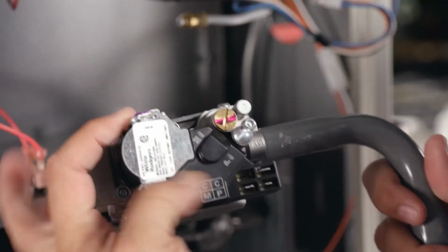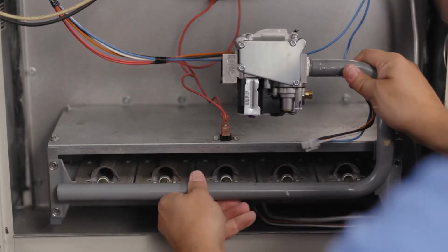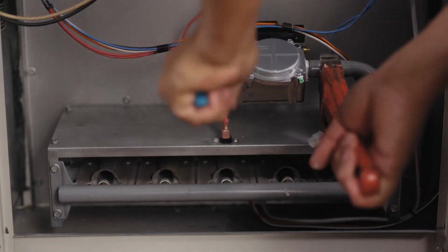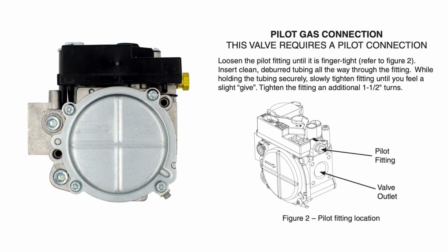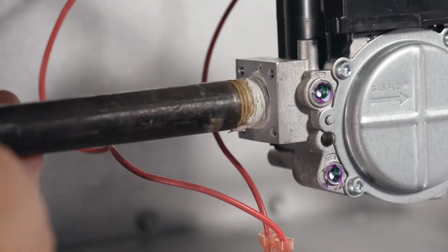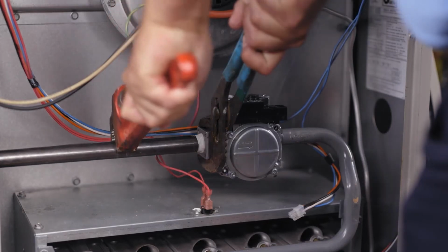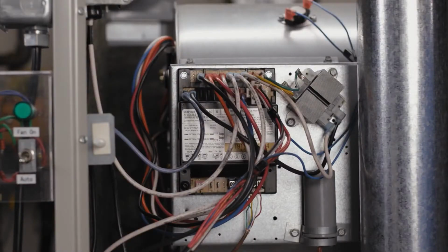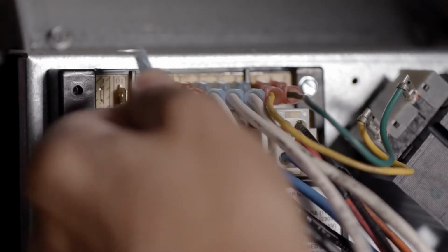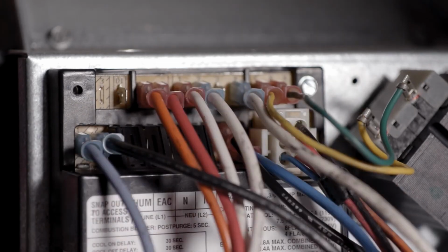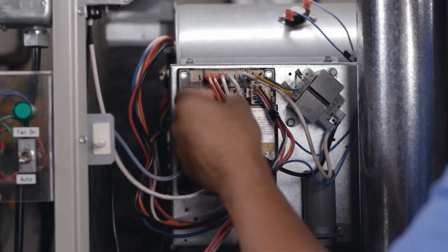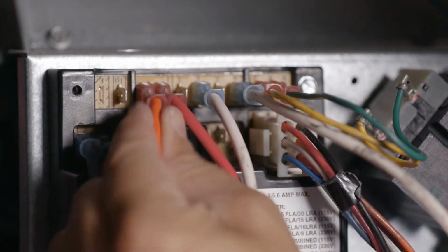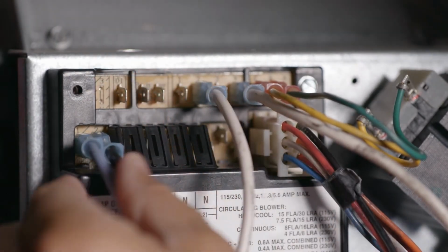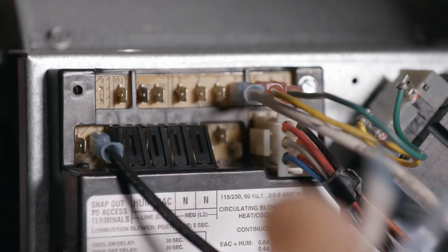Install the gas valve in the unit. Reconnect the gas manifold to the burners. Route the pilot tubing to the side of the gas valve and connect. And reconnect the inlet gas line. The fan timer is now ready to be unwired and removed. Remove the 120-volt hot and neutral inducer wires. Take note of what color wires are going to each terminal and remove the blower motor wires for common, cool, heat, and spares. Remove the 120-volt power and neutral wires.